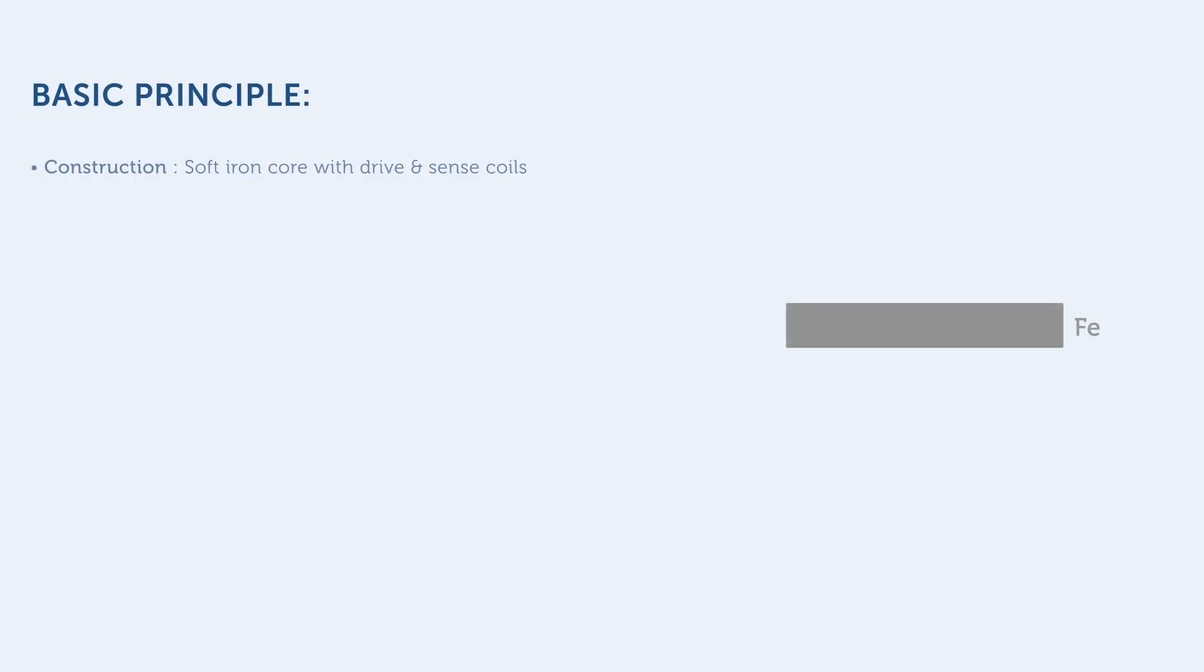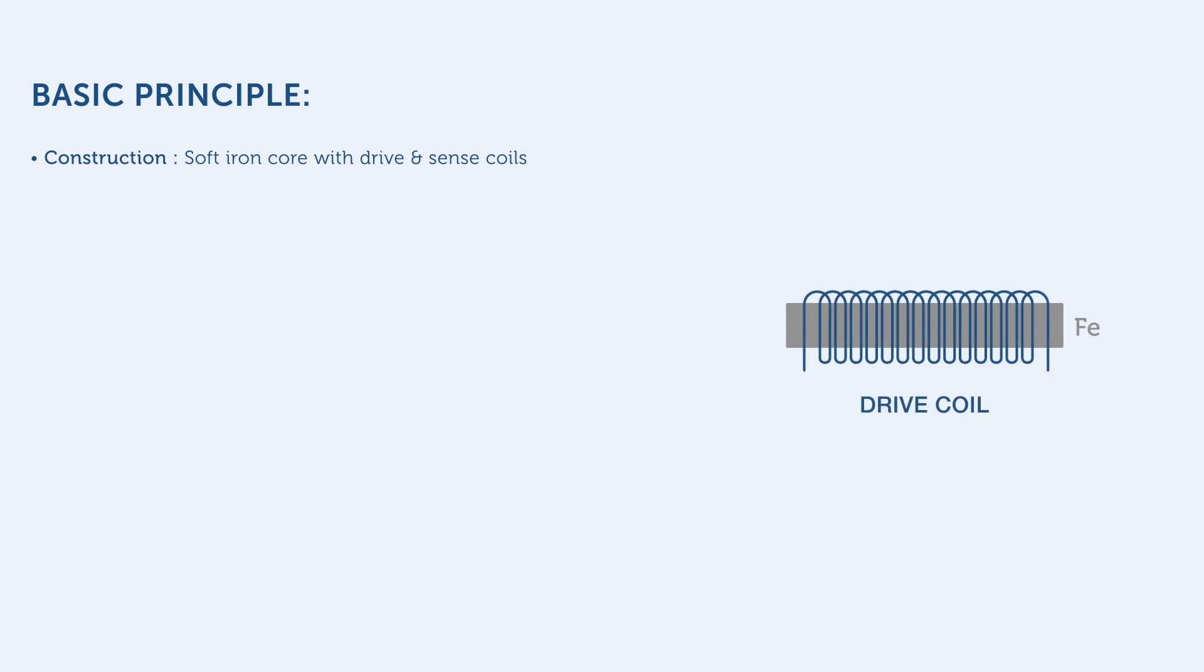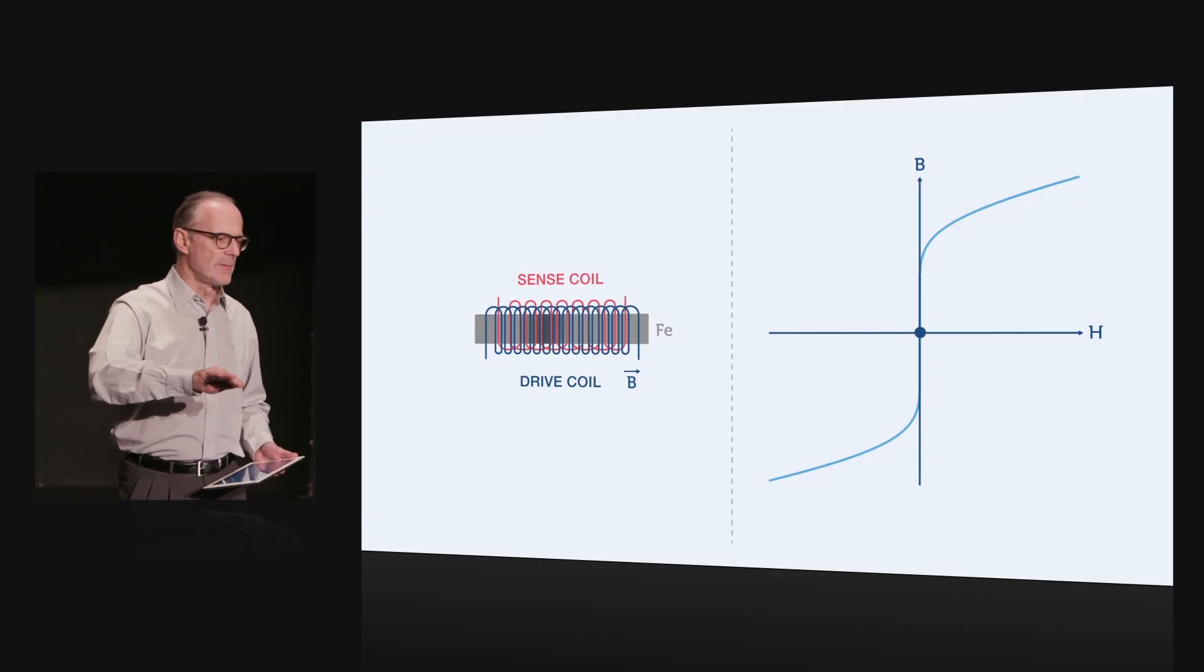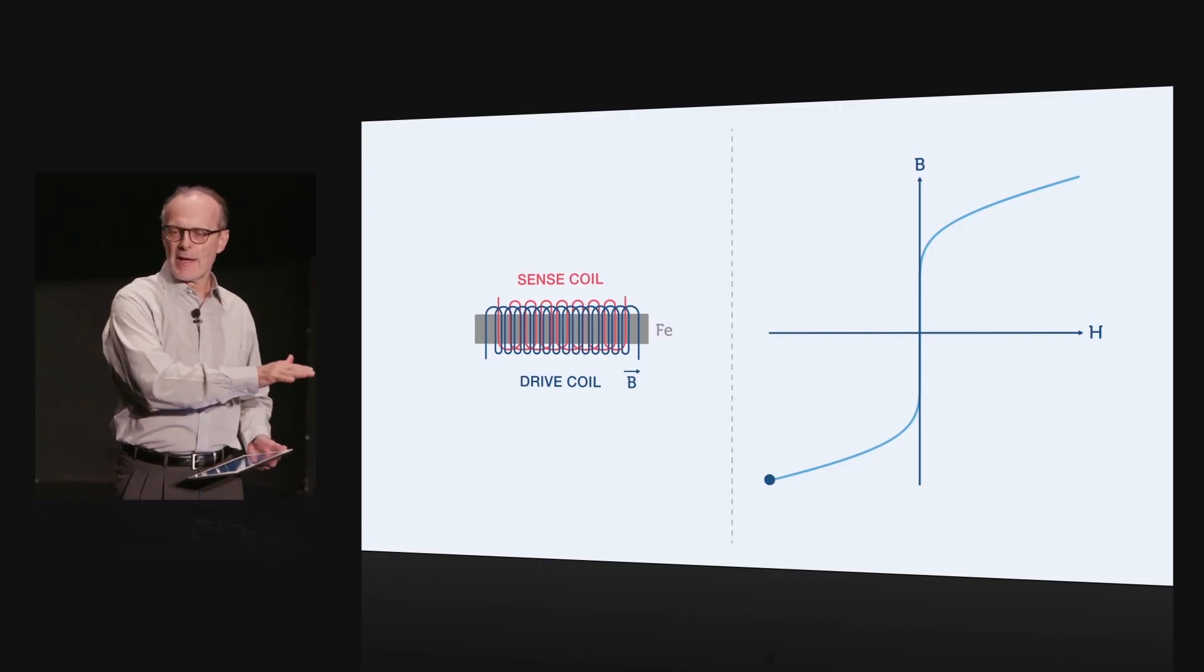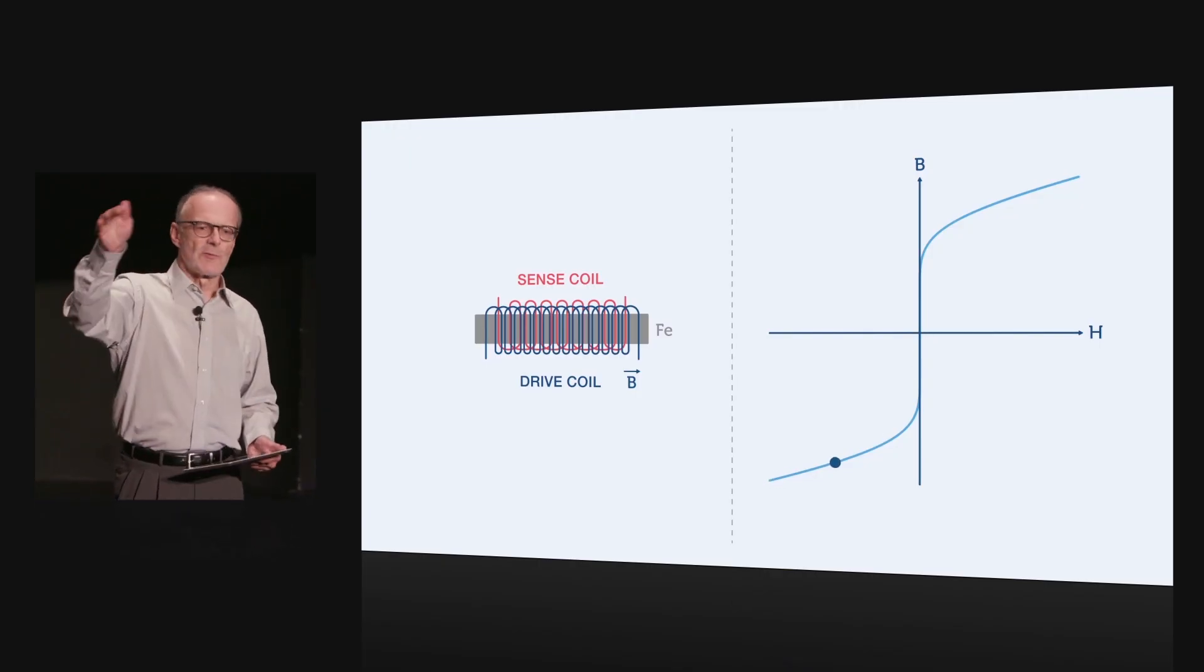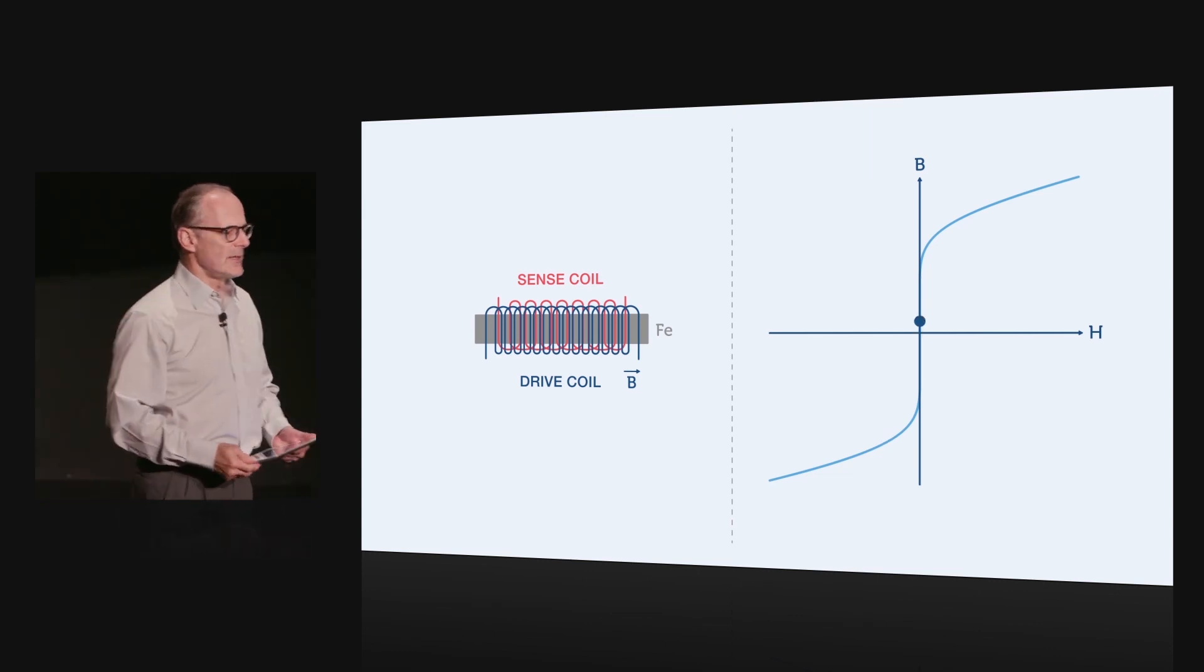A flux gate consists of three parts. There's a soft iron core, there's a drive coil, and there's a sense coil. The drive coil drives the soft iron core into saturation in the positive direction, back out of saturation, and into saturation in the negative direction. So it traverses the entire hysteresis loop.